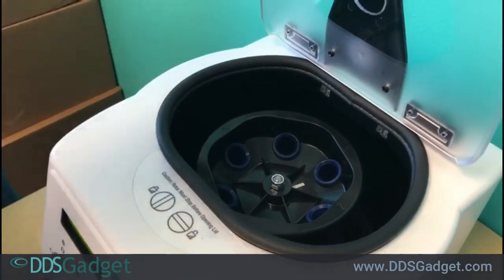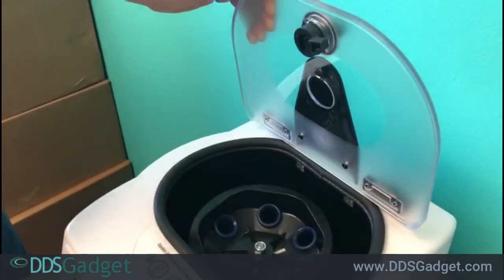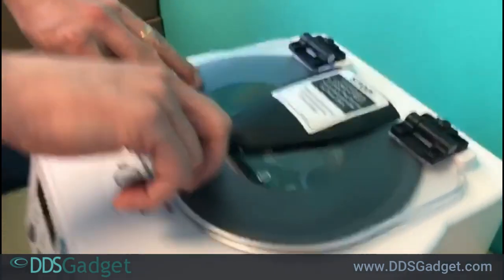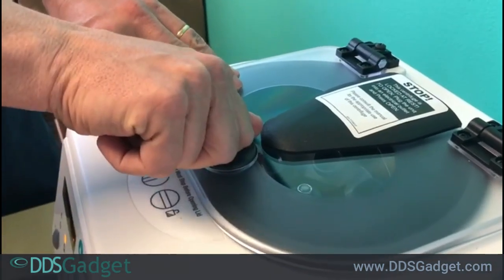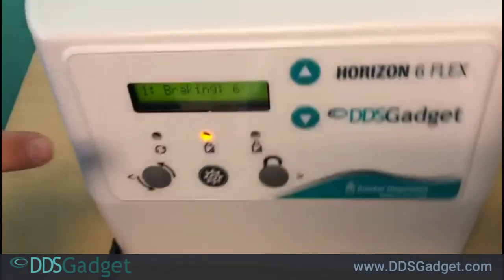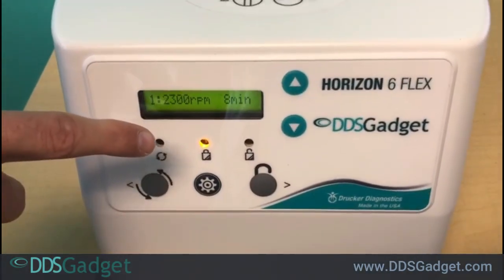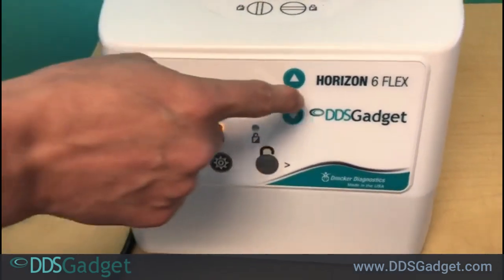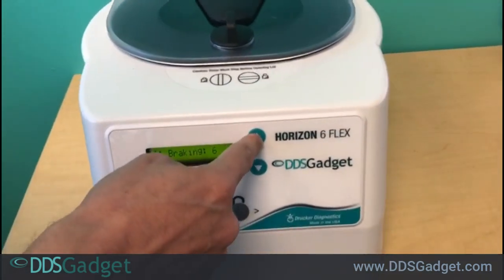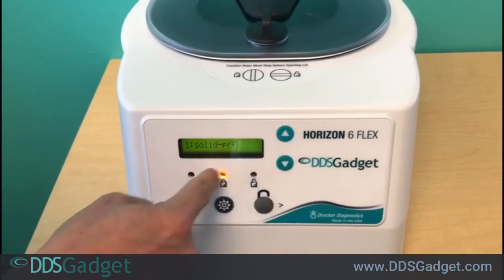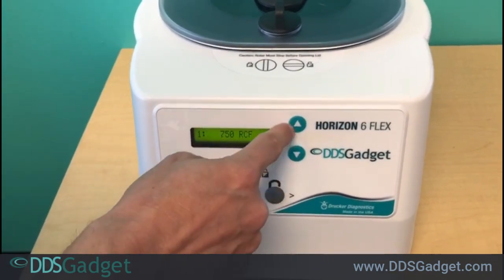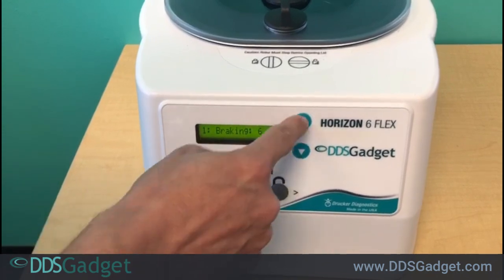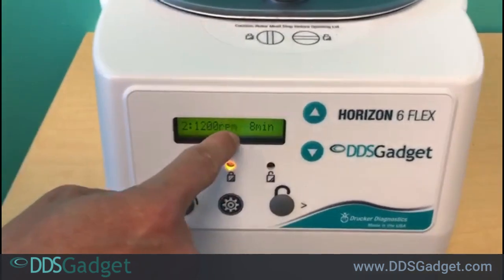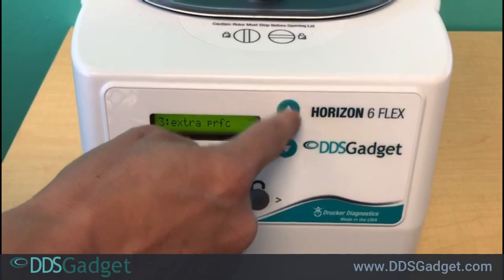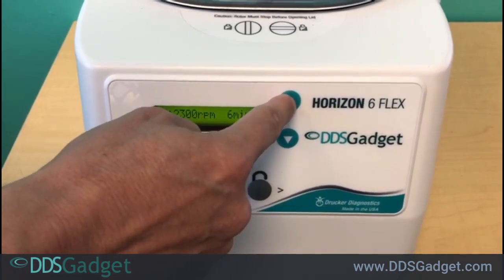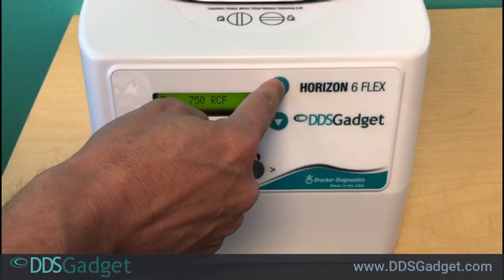After you place the tubes into the centrifuge, you would then turn the knob on top to lock the centrifuge, and then a light will show up in the front of the centrifuge to show that it is locked. You can then use the arrows to choose the cycle that you want. The first cycle over here is for solid PRF plugs and membranes. The second cycle that's preset is for liquid PRF or IPRF. And then you have custom settings if you choose to program those custom settings, which we'll get into in the next video.